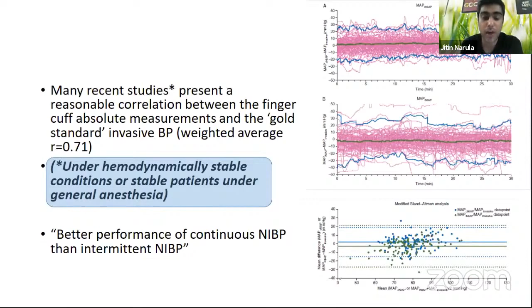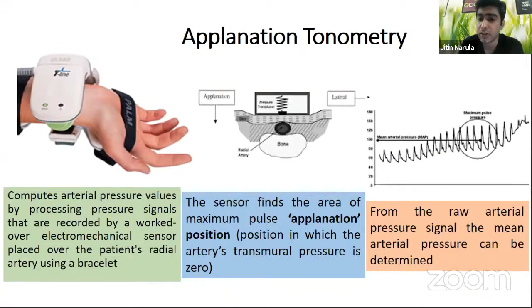The applanation tonometry technique computes the arterial pressure values by processing pressure signals that are recorded by an electromechanical sensor placed over the patient's radial artery using a bracelet. The sensor finds the area of maximum pulse, or the applanation position, in which the artery's transmural pressure is 0. From the raw arterial pressure, the mean arterial pressure can be determined. This waveform is then scaled according to a proprietary algorithm in the T-line monitor based on biometrical data to derive systolic and diastolic blood pressure. The waveform is also then used to estimate the stroke volume from the area under the curve.